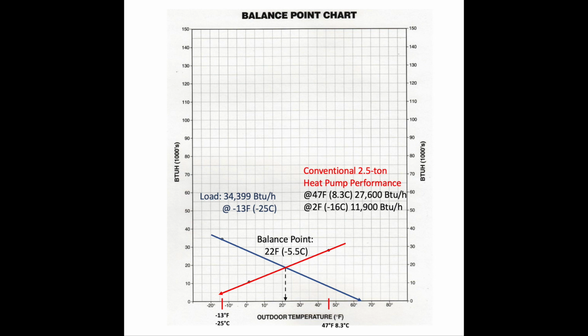That's the point where second stage is going to call. That's the point where the heat pump is running out of steam and it needs some help. In the old days with conventional heat pumps, we were using electromechanical controls, and we needed to set a balance point so that in the house you wouldn't get a drop in temperature. But we also wanted to make sure that the heat pump was delivering as much heat as it possibly could. So we didn't want the heat pump shutting off too early, nor did we want the backup heat coming on too soon. So the balance point chart is what helped us to determine when that second stage was going to call.